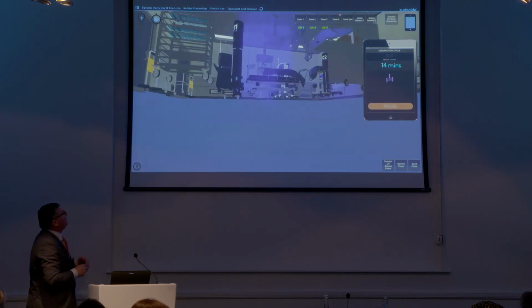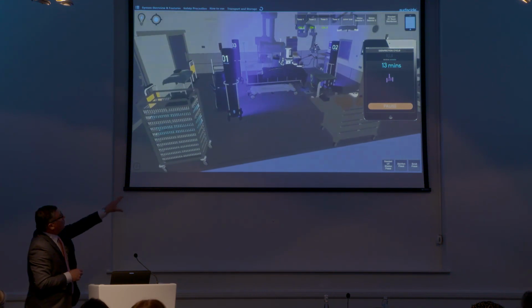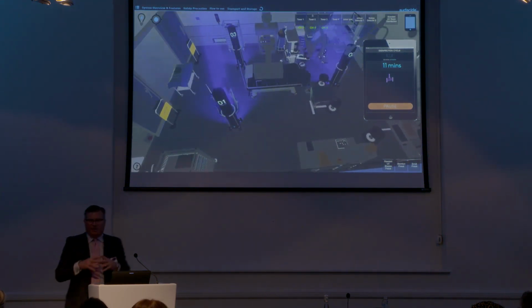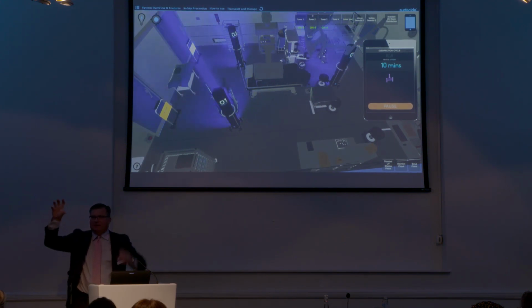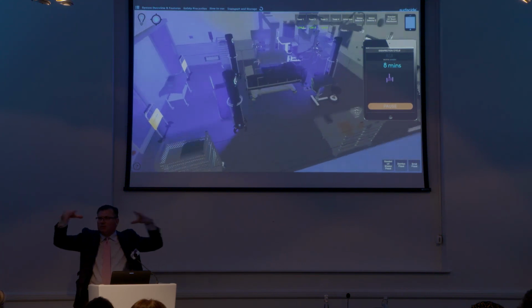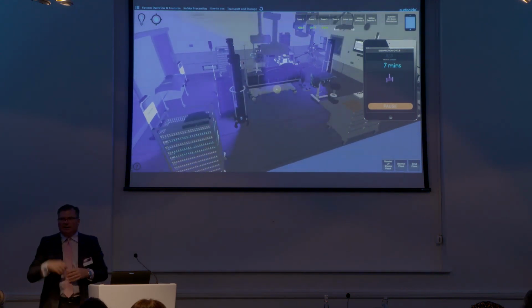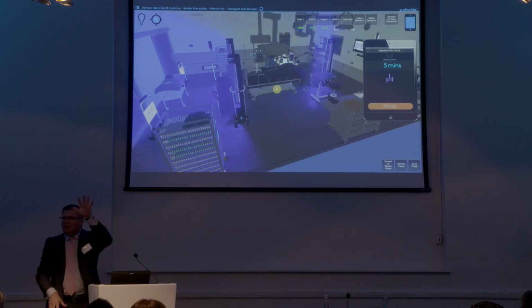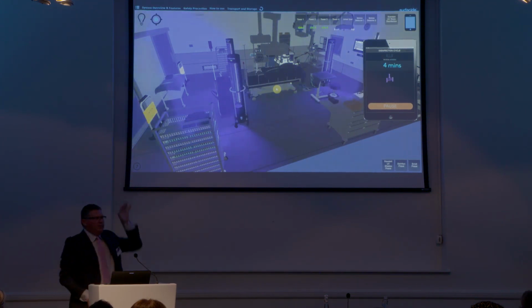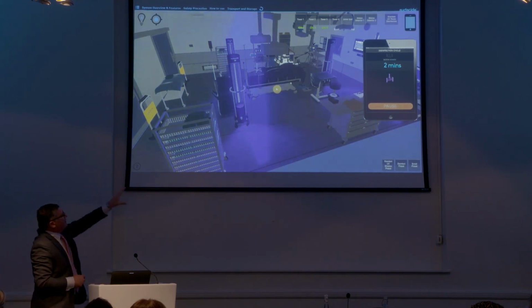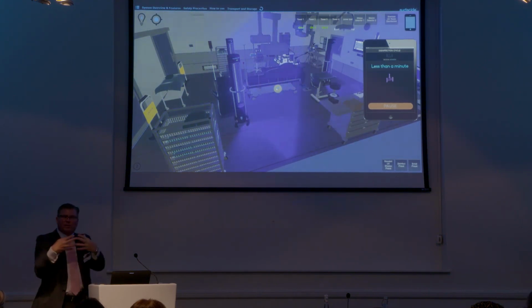What you can see though, this is designed to show you the floor to ceiling coverage. In an operating theater particularly, there's lots of objects at heights. There's more and more monitors coming into rooms, there's more booms, there's obviously the overhead lights. And so we want to make sure that we're disinfecting the entire room column all the way from the ceiling to the floor. You can also see how the 3 towers in triangulation overcome the shadows.